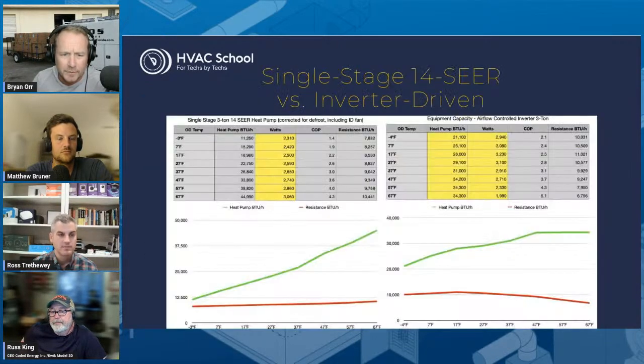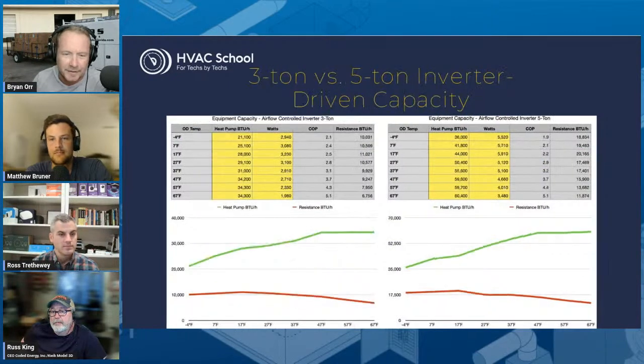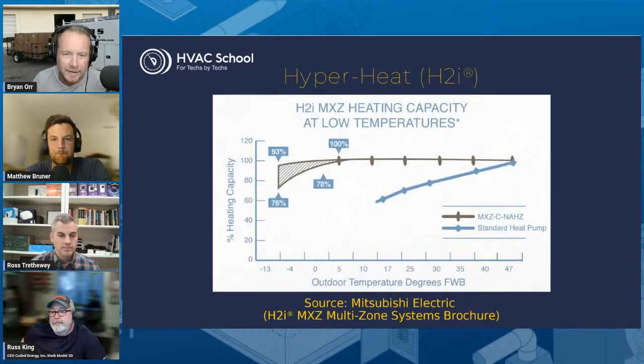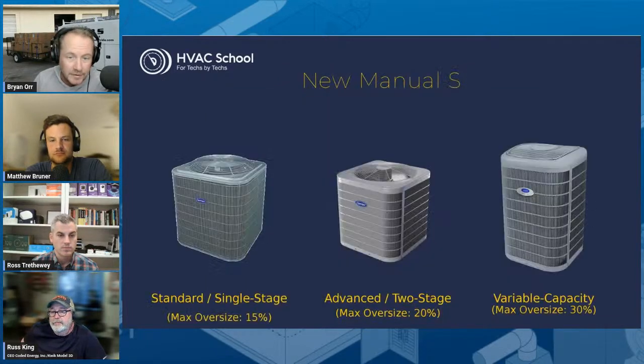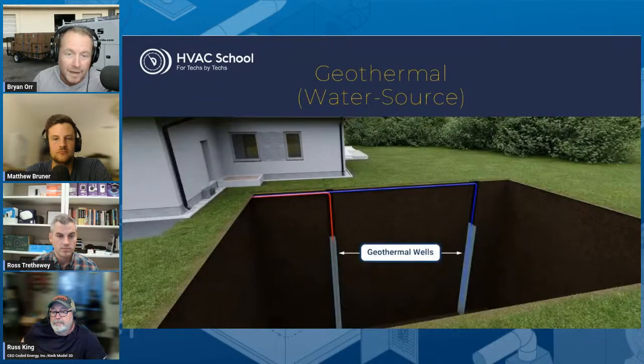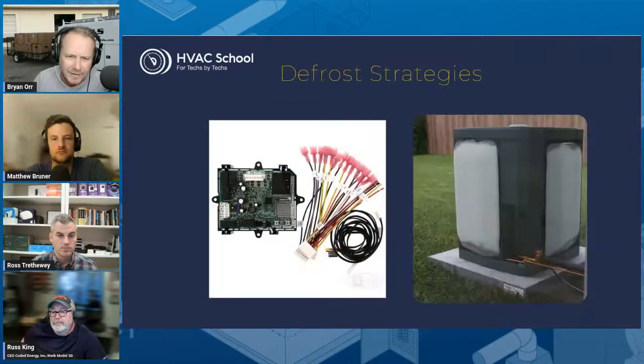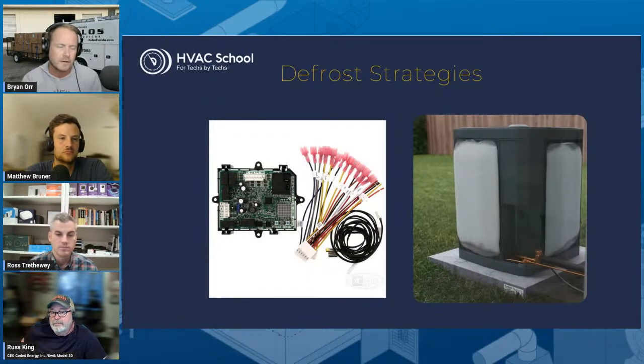The other thing that I wanted to mention there is, and we got some charts on that, I'm not going to dwell on that, just kind of showing how you do have some pretty amazing abilities to continue to heat even down to low ambient conditions. But a lot of that is also due to improved defrost strategies too, where we're really going to demand defrost nowadays, and more. And what that does is we only defrost when we need to.